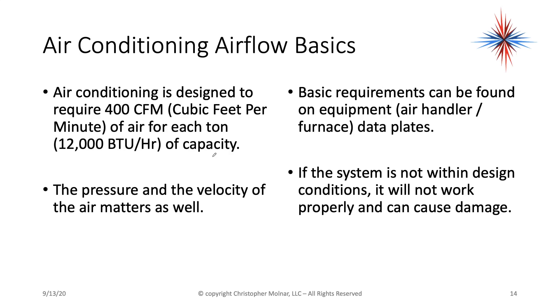Air conditioning is designed to require 400 CFM — cubic feet per minute — for each ton of capacity. A ton of capacity is 12,000 BTUs per hour. The pressure and velocity of the air matters as well. Basic requirements can be found on the equipment data plate on your air handler or furnace. If the system is not within design conditions, it's not going to work properly and can cause damage.